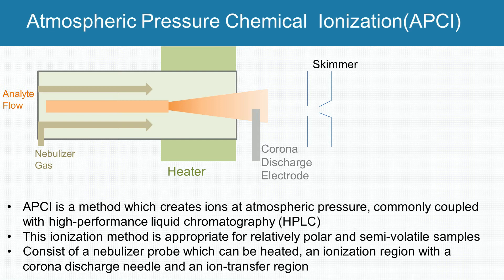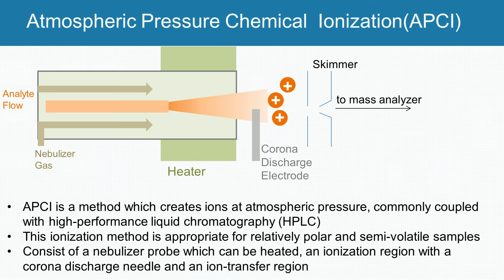A corona discharge is where a highly charged electrode creates an electric field strong enough to ionize nearby molecules. The resulting sample ions then pass through a skimmer into the ion transfer region. Then, ions are injected into the mass analyzer for detection.